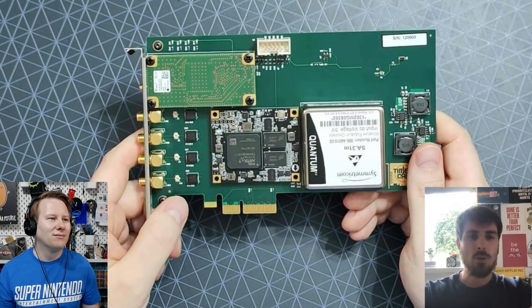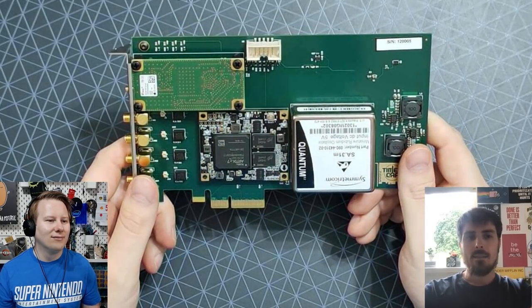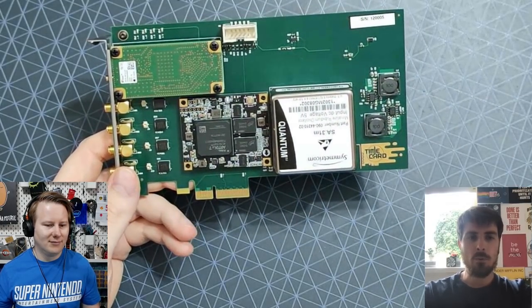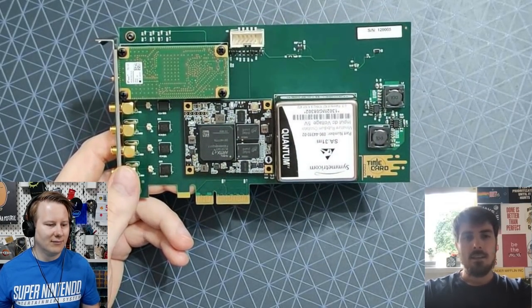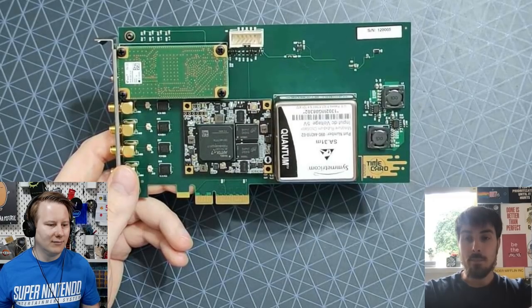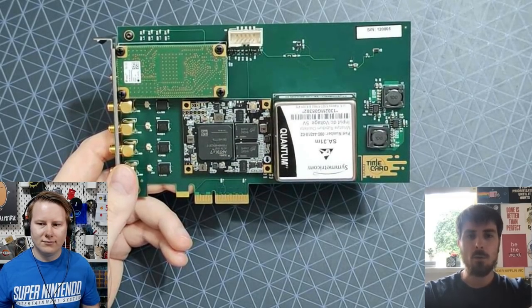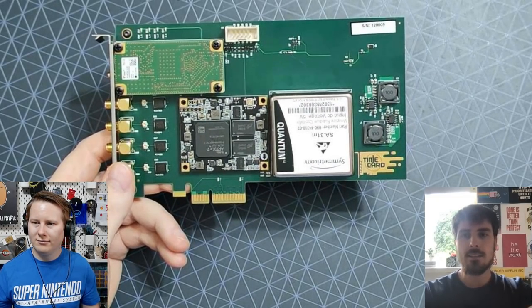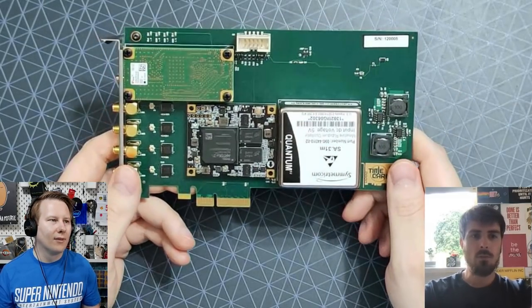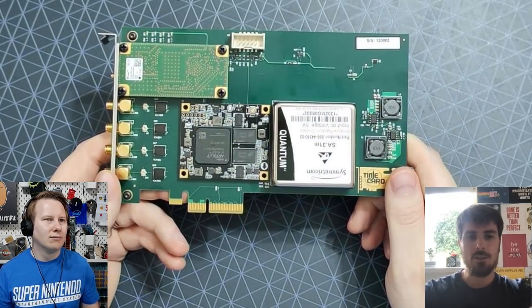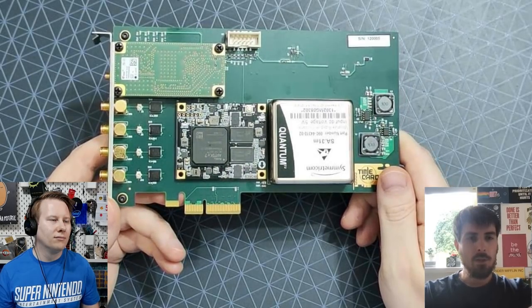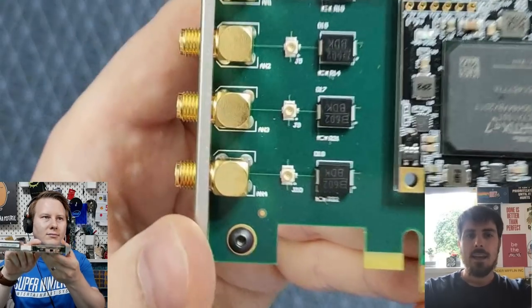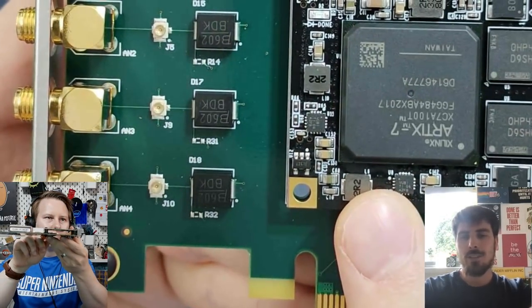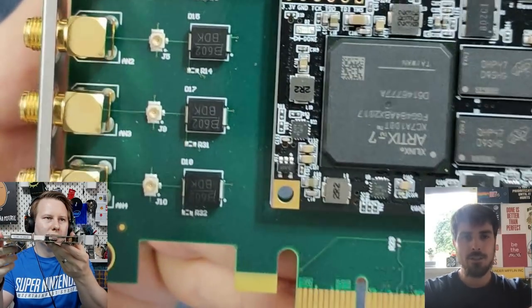So the atomic clock is sitting there and basically ensuring you have this important backup in case this happens. The atomic clock itself drifts approximately 1 microsecond a day, depending on the quality of the atomic clock and the oscillator in general. And there is an FPGA which basically merges those two together, and we call it between ourselves some sort of a time engine.